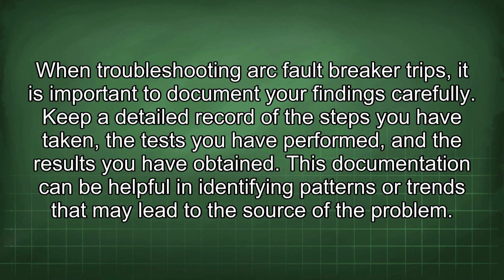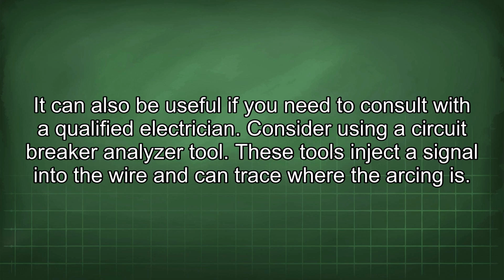When troubleshooting arc fault breaker trips, it is important to document your findings carefully. Keep a detailed record of the steps you have taken, the tests you have performed, and the results you have obtained. This documentation can be helpful in identifying patterns or trends that may lead to the source of the problem. It can also be useful if you need to consult with a qualified electrician.